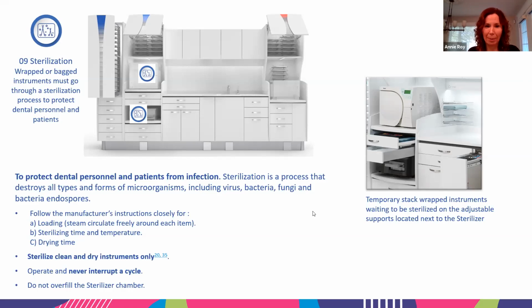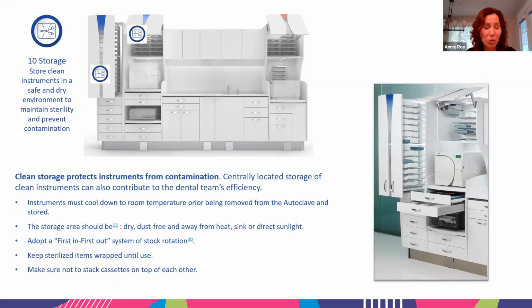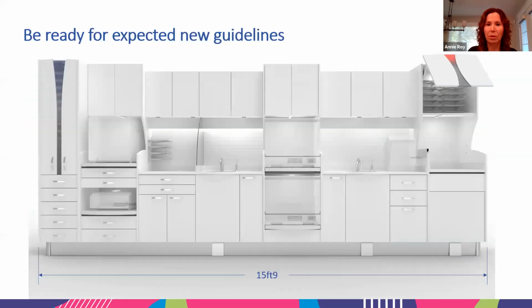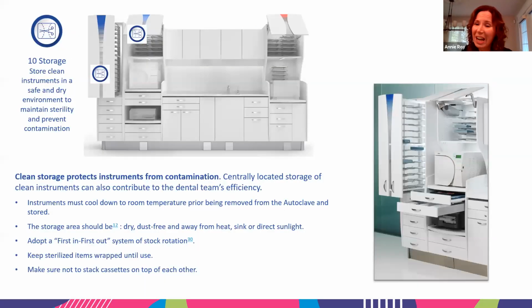Sorry, now it had to happen, my PowerPoint decided to freeze. So the next step, like I said, is storage. Clean storage, of course, to protect instruments from contamination, again centrally located. Instruments must ideally cool down to room temperature prior to being removed from the autoclave and stored. The storage area should be dry, dust-free, away from heat, sink, or direct sunlight.